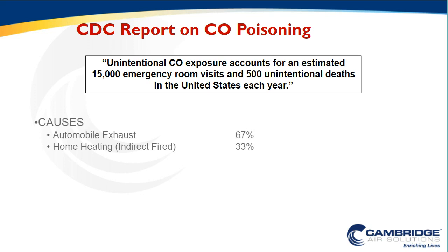And inside that study, what they found is that about 2/3 of those CO exposures, the root cause, was actually automobile exhaust, such that automobiles were creating the CO exposures that led to an unsafe environment. About 1/3 of those situations were caused by a home heating system, actually an indirect fired combustion device. And inside that study, they were not able to find any single CO poisoning, any CO exposure, that was caused by a direct fired combustion device, such that a system that is designed to deliver the product of combustion to the space was actually not the cause of any of the CO exposures across the U.S., even though they are widely deployed in many commercial spaces.